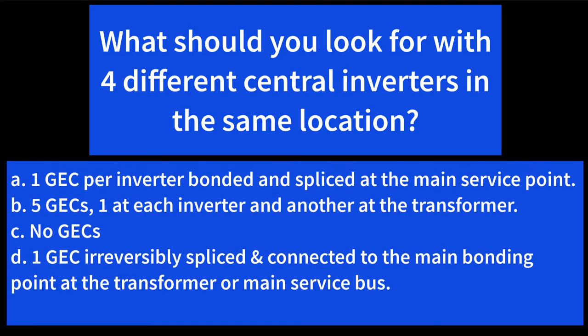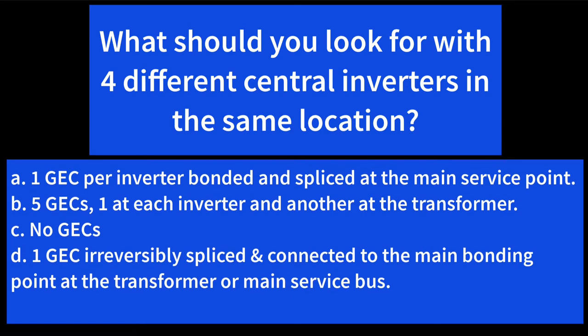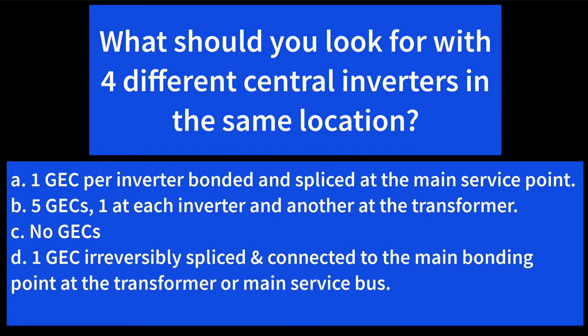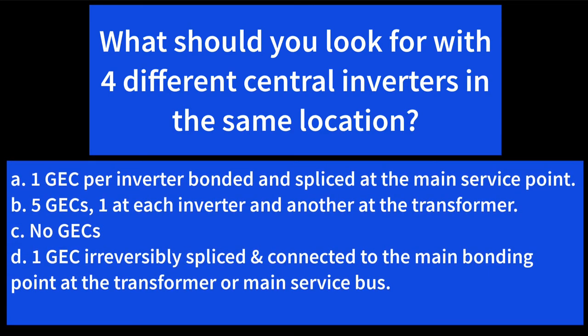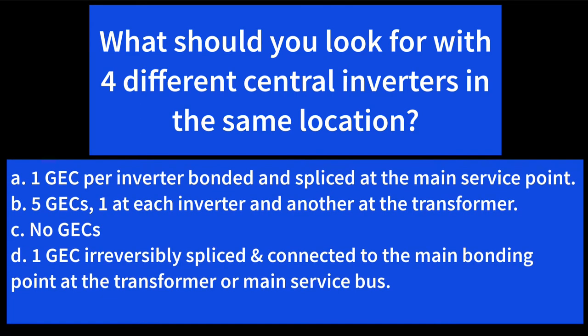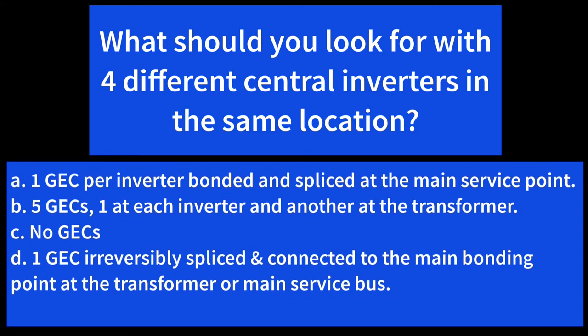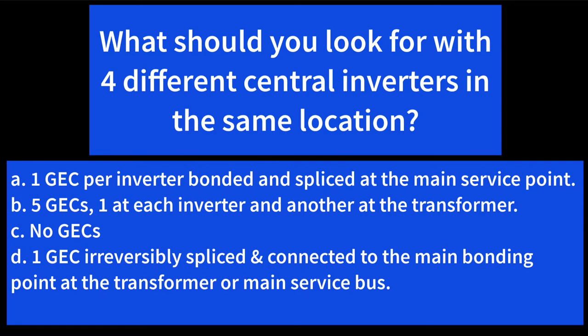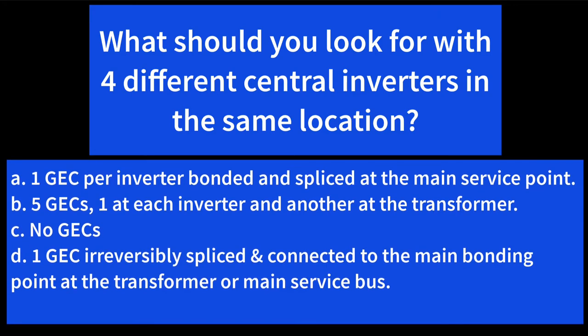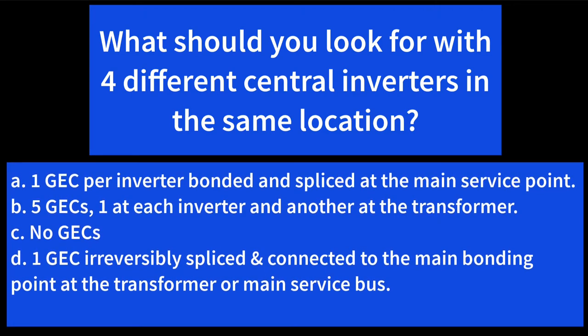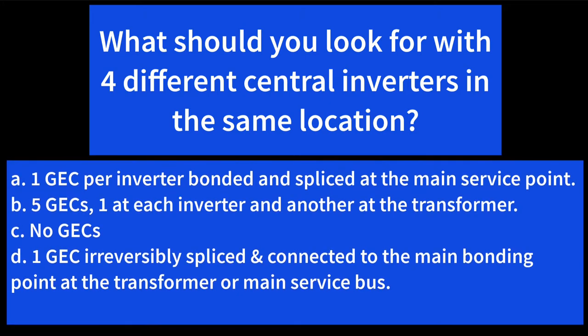B, 5 grounding electrode conductors, 1 at each inverter and another at the transformer. C, no grounding electrode conductors. And D, 1 grounding electrode conductor irreversibly spliced and connected to the main bonding point at the transformer or main service bus. So this is a topic for the discussion that's going to go on for about 20 minutes.